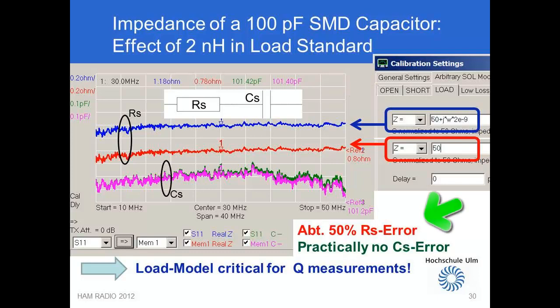Despite this, the error is 50% on the series resistance, while for the capacitance value hardly any influence is seen. The slightest change in the calibration load model has a great impact on the series resistance and thus the measured capacitor Q. As the imaginary part of the load standard in general is hard to determine and often unknown, it is very essential to have a quality load standard to compare with for its determination.